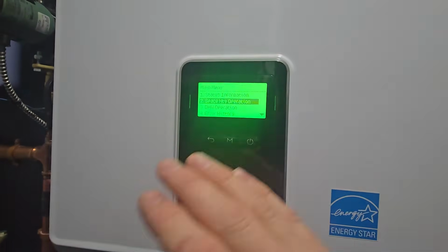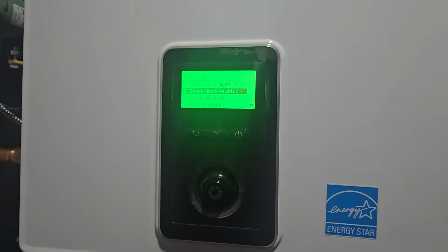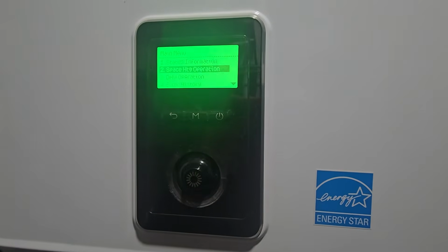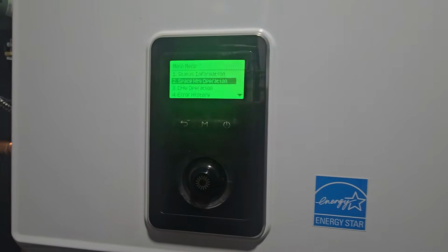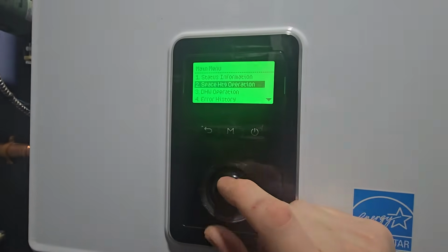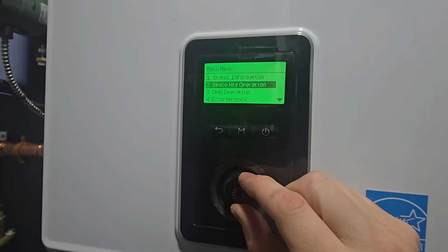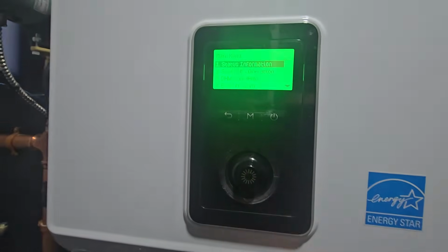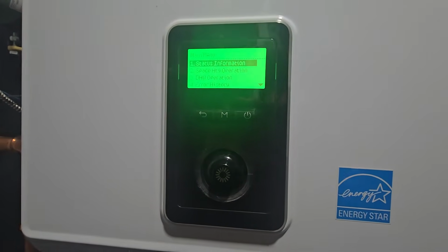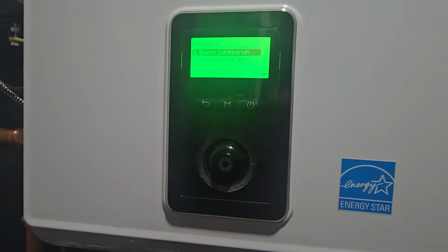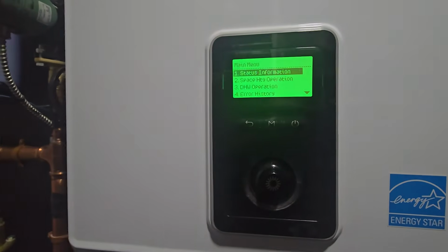And depending on the one you choose, that's going to follow a different heating curve depending on the outdoor temperature. So for example, if I choose high mass radiant, which would mean concrete, I don't want to ever give this thing 180 degree water. I want that highest temperature during those 0 degree days to only go up to about 120, 125. So it's going to follow that. Now, if I have baseboard, I want on those 0 degree days to be at 180. And then on the warmer days, it'll go down to a minimum amount of, I think, about 150 or so.